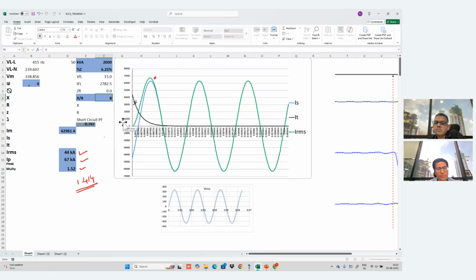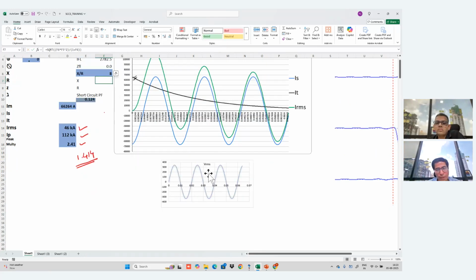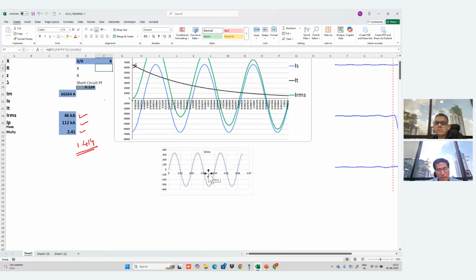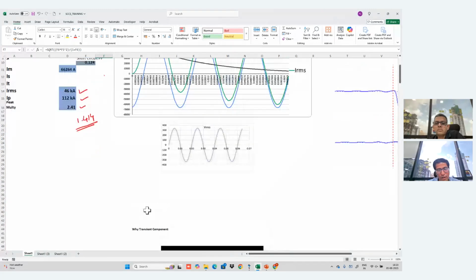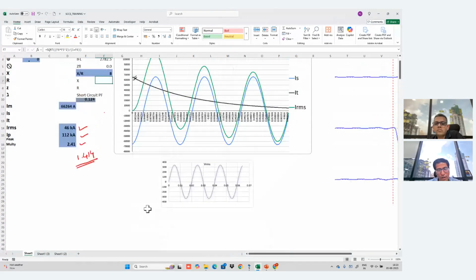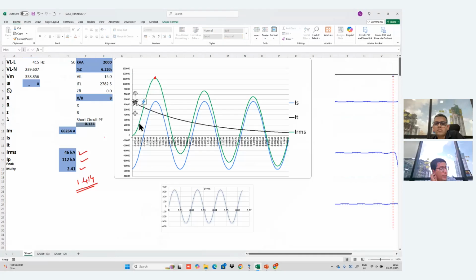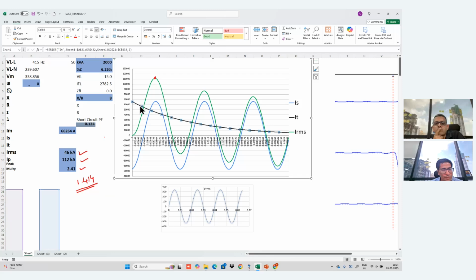Okay, the third question which everyone must be having in mind: where does this transient DC component come from, because we are not giving any DC current or DC voltage, and we do not have any DC component in the voltage. Then how does this DC current come about? Basically this is common everywhere. It is common even to a capacitor. When we switch on a capacitor, initially there is a high inrush current. When we switch on a motor, we also have a high inrush current, and all these inrush currents have this DC component present.